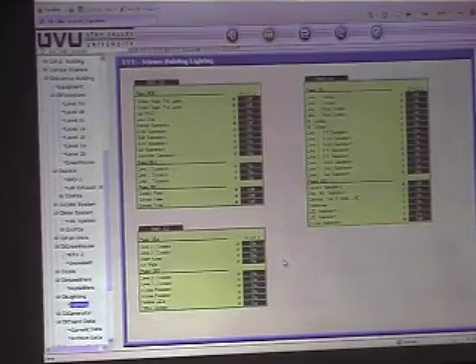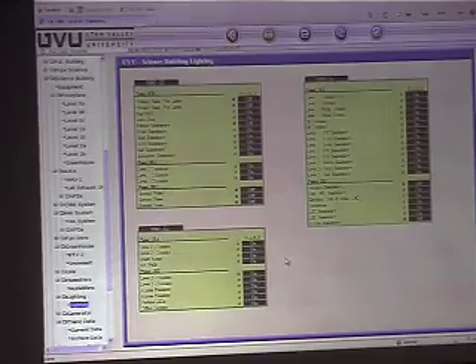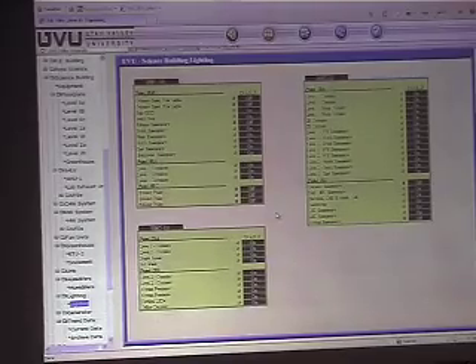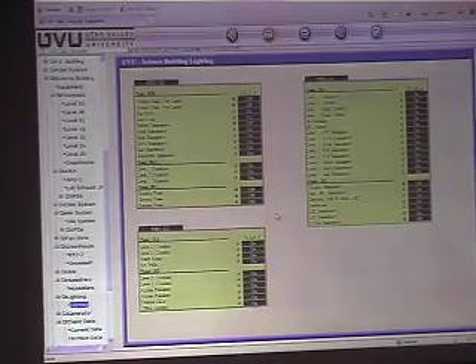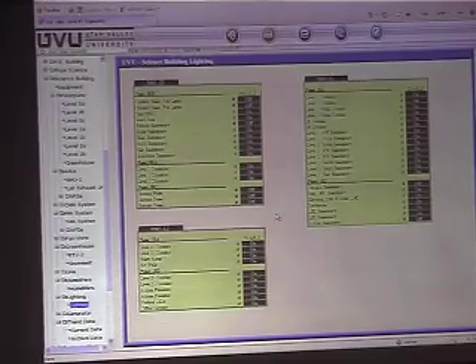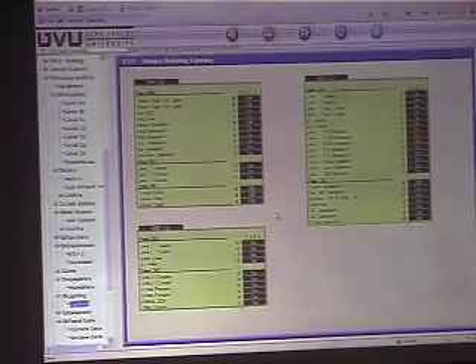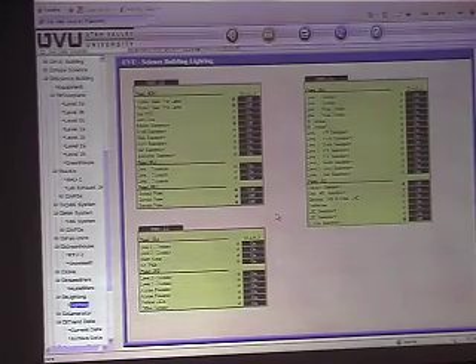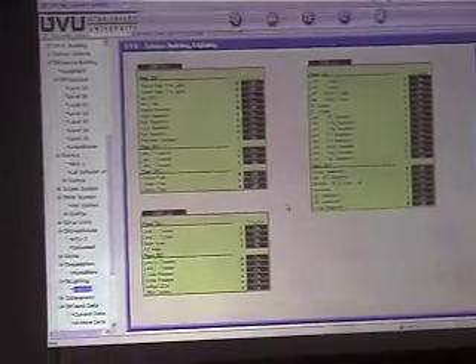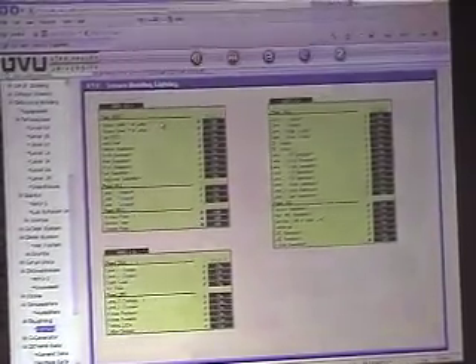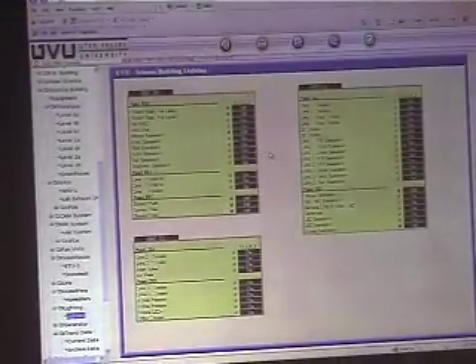No photocells, but there are 3 photocells, and I need to add them to this. We just added them a couple of weeks ago. Originally, we thought all the lighting was going to operate just off of scheduling, but then we found that there were photocells up here, and so we just had to tie into them. They are tied into the logic. I just need to add them to the graphic here. Will they be controlled to everything or just certain sections? There are certain sections, and I'll make a comment out here next to the zone that shows whether it's photocell or schedule only, so you'll know if it's supposed to be on or not.